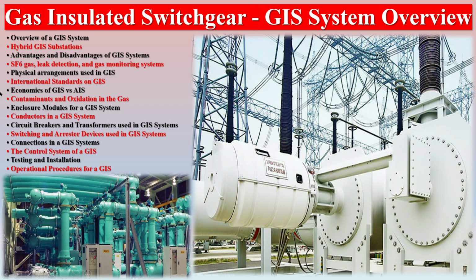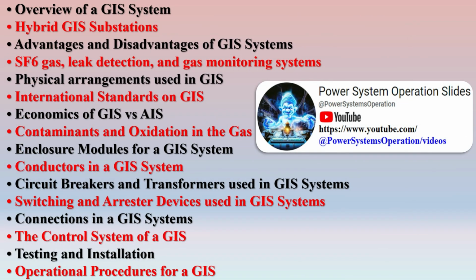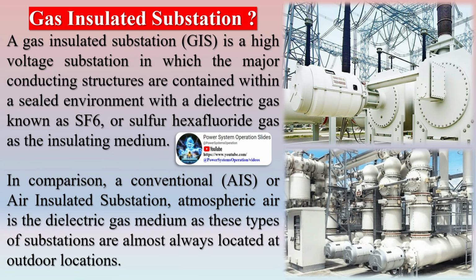A gas-insulated substation (GIS) is a high-voltage substation in which the major conducting structures are contained within a sealed environment with a dielectric gas known as SF6, or sulfur hexafluoride gas, as the insulating medium. In comparison, in a conventional AIS, or air-insulated substation, atmospheric air is the dielectric gas medium, as these types of substations are almost always located at outdoor locations.